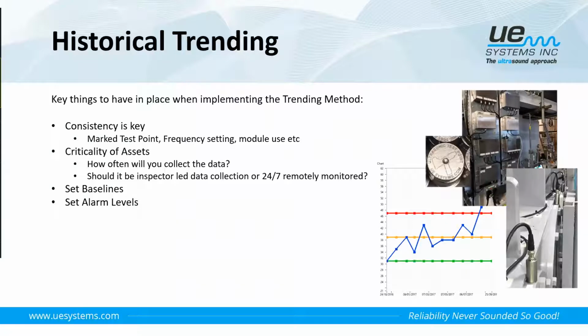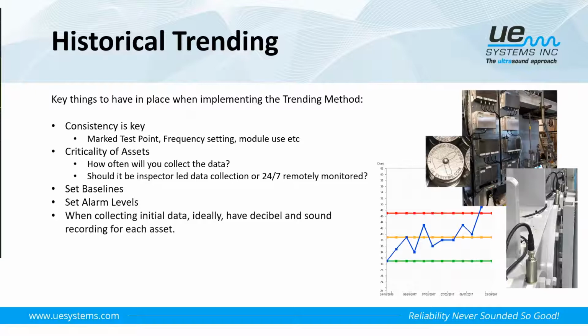We then need to go on to setting our baselines. And once we've set our baselines, we can then look at setting our alarm levels. And when we start to collect our initial data, like our baselines, for example, we will have a decibel value, but hopefully we can take sound recordings with the device that we have, so we can have something to reference each time we take a reading. It's always good to be able to refer back to something or a recording if you haven't inspected it for maybe a month or two. Is access an issue? You need to ask yourself. Can I get access with a man-portable device? Do I need to install remote access sensors to help me with my program to collect that data each time?